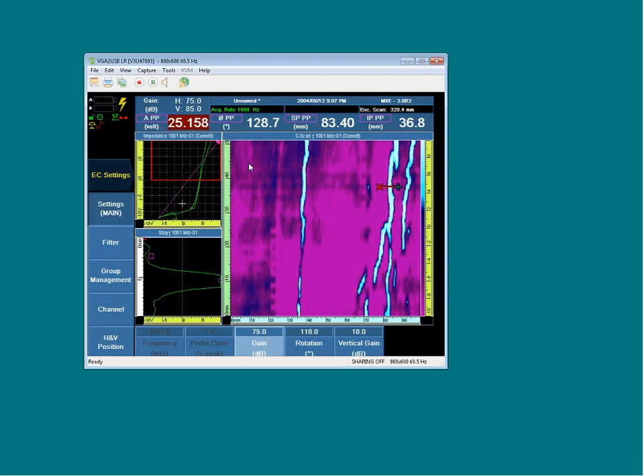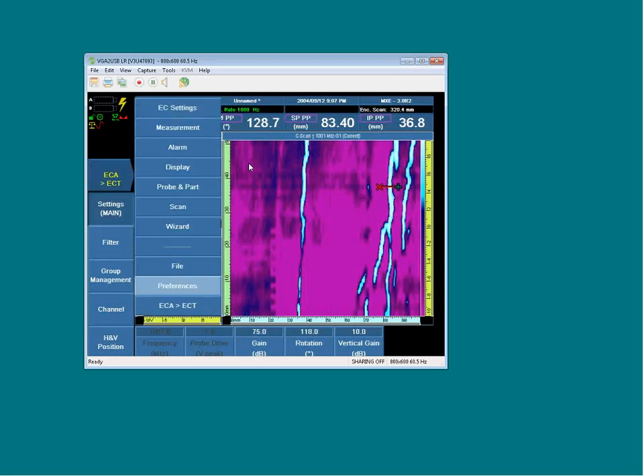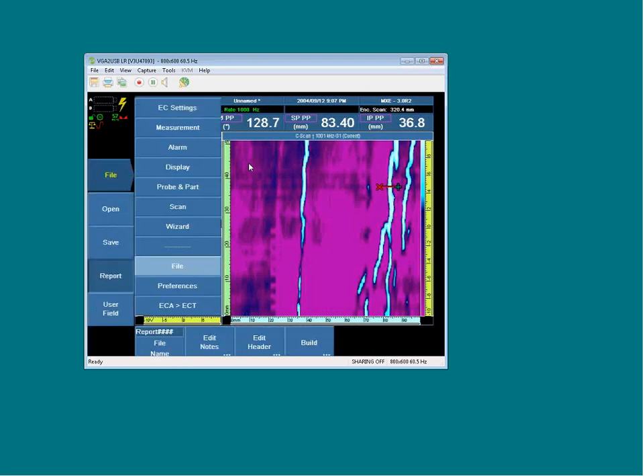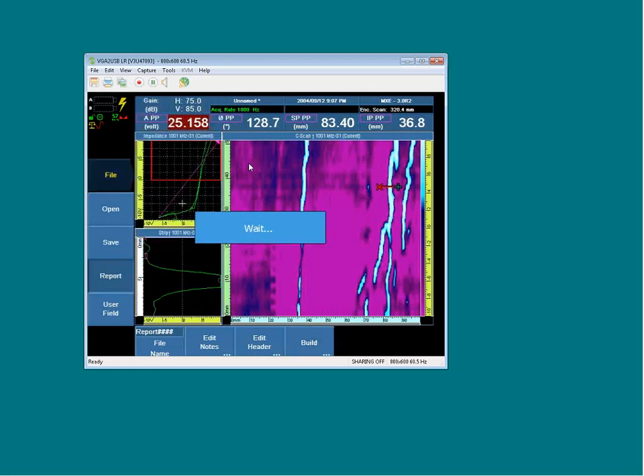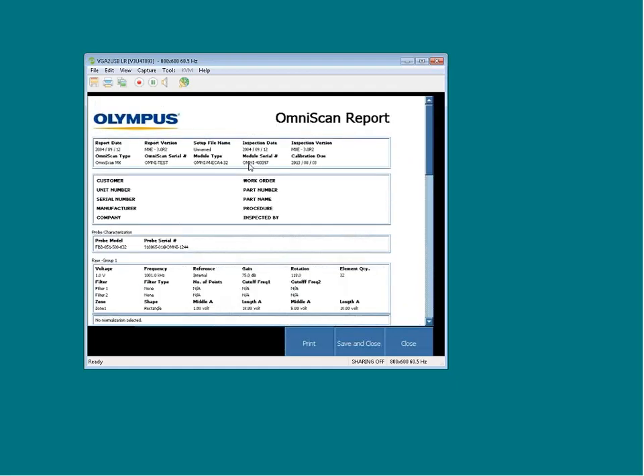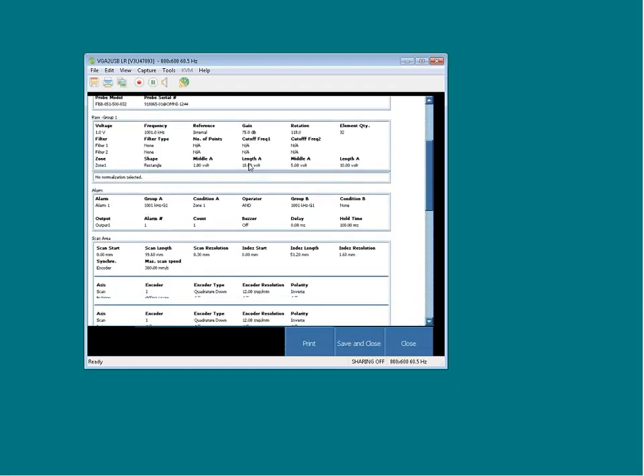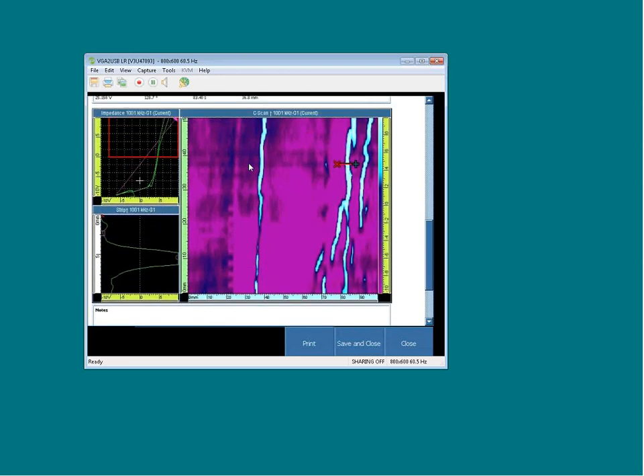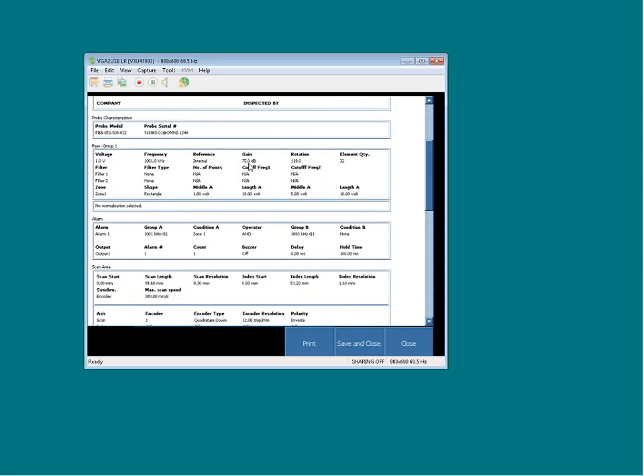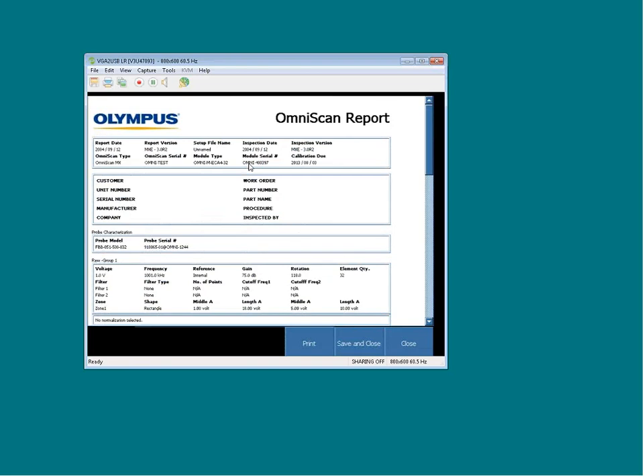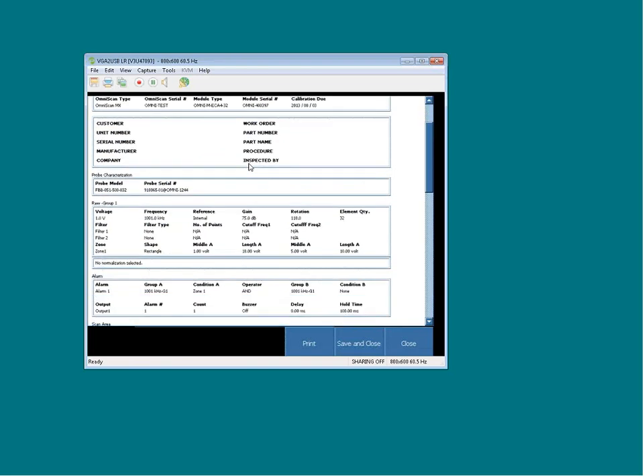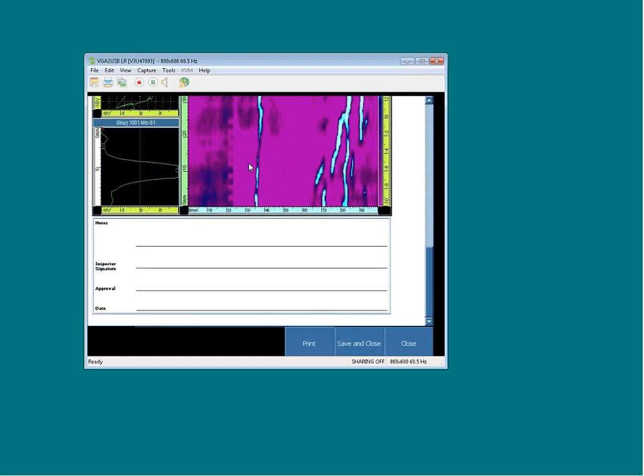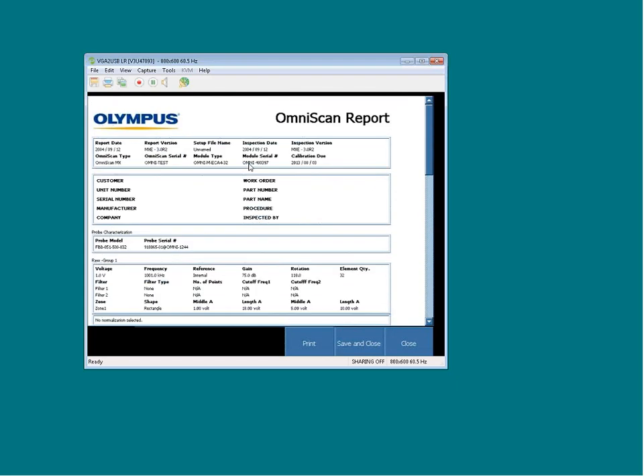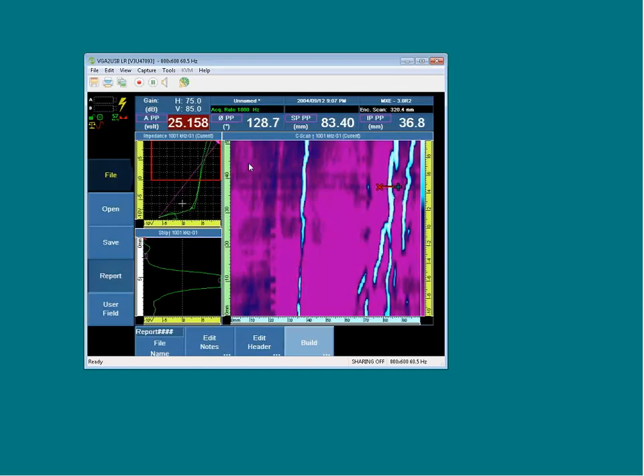So once you're happy with those results, it's possible to go to File menu, get to Report, build a report, and you basically, at the touch of a key, you get an instant report that can be printed, shared, and saved. So that's the screenshot. And now all the eddy current array parameters, the particulars about the customer, unit number, and all that stuff. And at the end, there's the QA signature and approval part. So again, that can be saved, and for now, I'm just going to close it. So that was the report capability of the OmniScan.